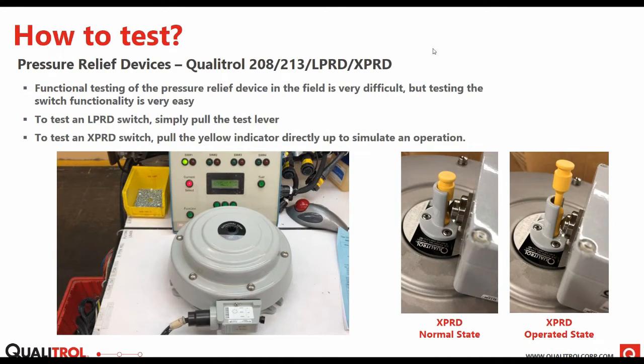So let's move on to our pressure relief devices. Here specifically, we're going to be talking about our large pressure relief device and our extra pressure relief device, which are LPRD, XPRD, sometimes the 208 or 213. So full functionality testing of the pressure relief device is very difficult in the field. You would need to have a tank that you could pressurize to the relief pressure to simulate a blow-off of the pressure relief device.